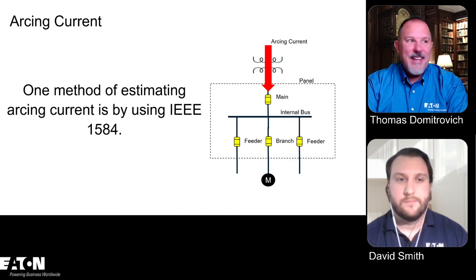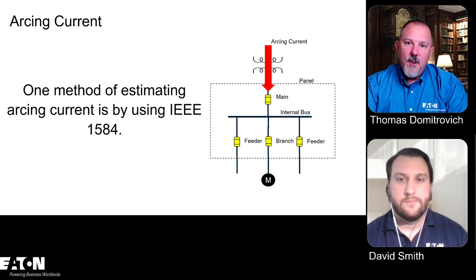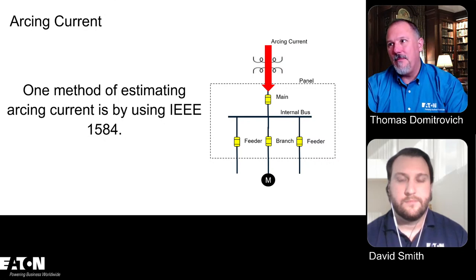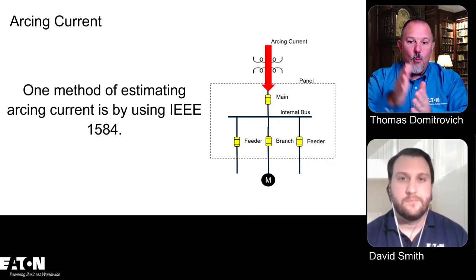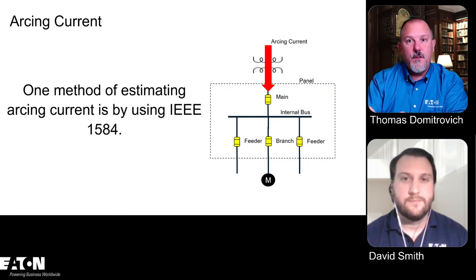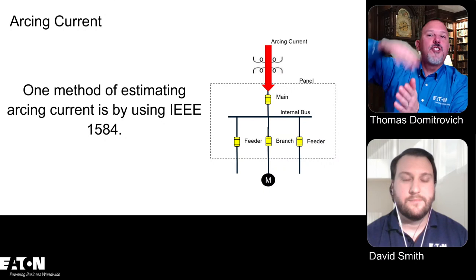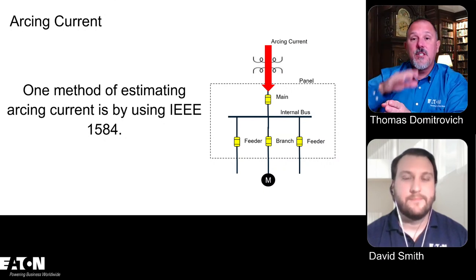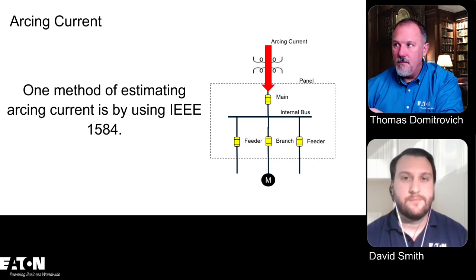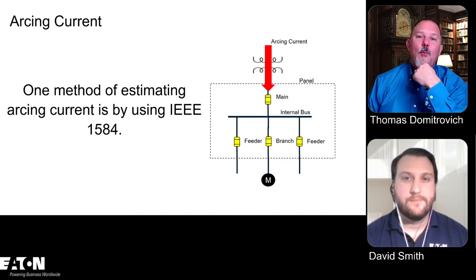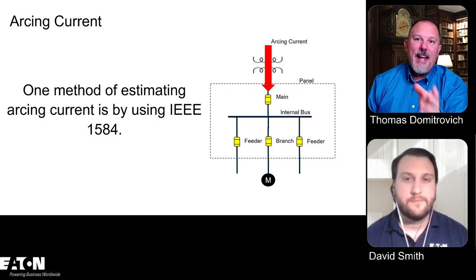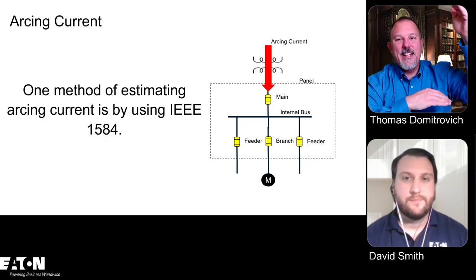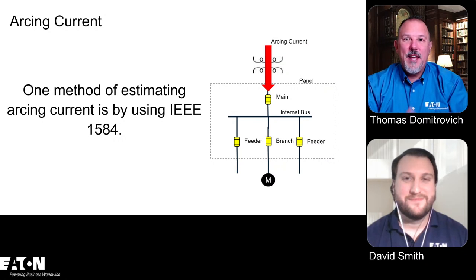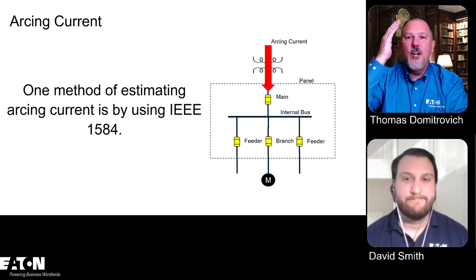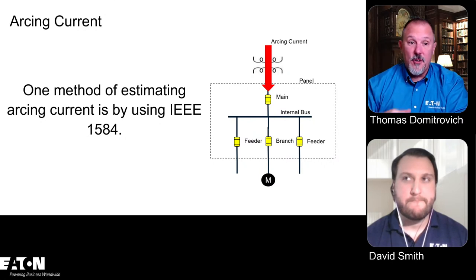So here was my issue with that. When I used the Ralph Lee method, I did 106,000 amps on an overcurrent protective device. And I wasn't into the instantaneous region. I wasn't into the current limiting region of the fuse. Okay. And the incident energy was high. I needed to get well above 106,000 amps to get the arcing current in a fast clearing time. But I went to 107,000 amps in SKM and calculated it. And I went from like 100 calories to 2 calories because it used the Ralph Lee method. And the Ralph Lee method does not calculate arcing current. It looks at what is the trip time at the three-phase bolted fault current value.